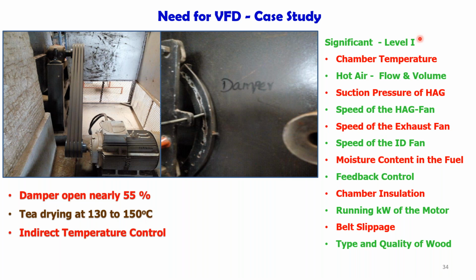Now, these are the significantly affecting factors. We listed some of the significant factors with the help of the investigation. We also recommended putting a variable frequency drive on this motor, for the blower, and removing the damper. That will be a good idea.